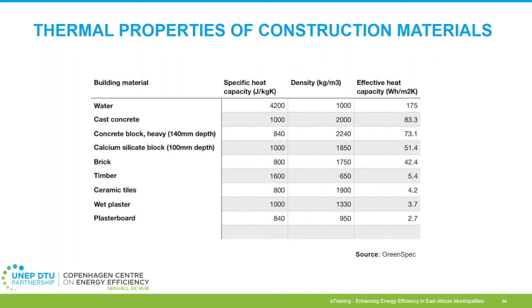To determine the thermal mass of a material, we need to know its volumetric heat capacity, which can be assessed by multiplying its density with its specific heat capacity. As this table shows, heavyweight materials such as concrete and brick have a high volumetric heat capacity, so a building constructed with these materials would have high thermal mass. Lightweight materials such as timber and insulated panels have a low volumetric heat capacity and therefore low thermal mass.